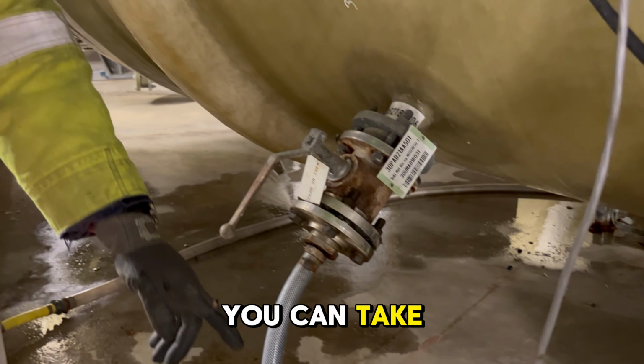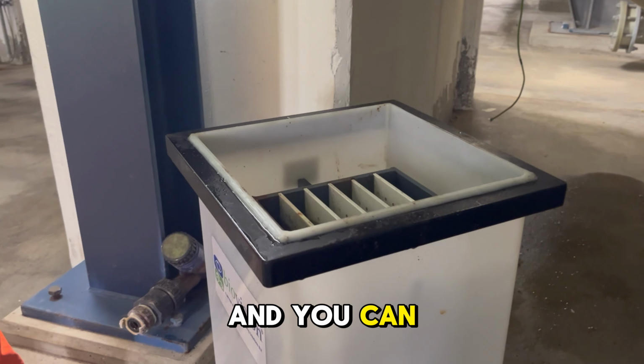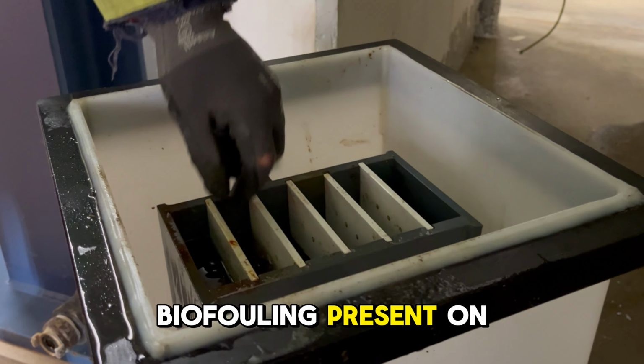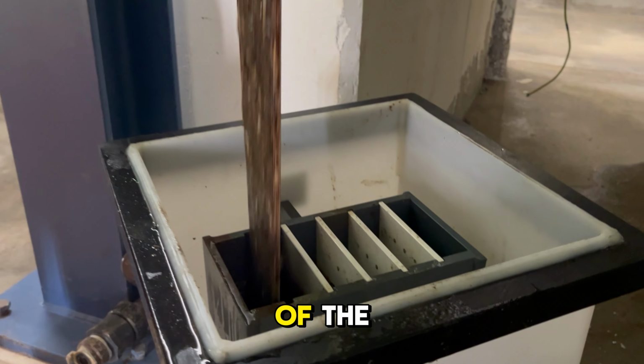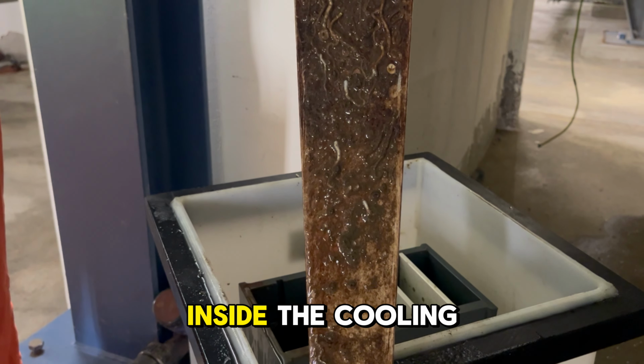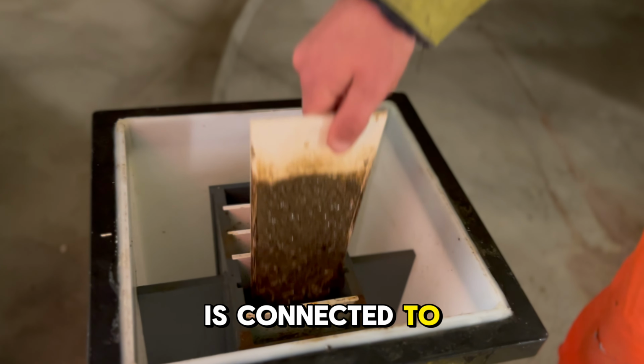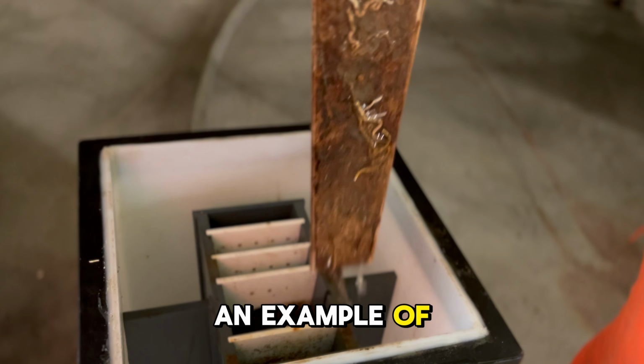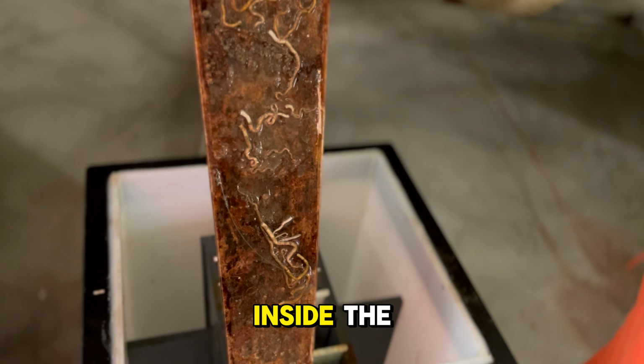In the Biovision monitor you can take out the coupons quite easily, and you can see if there's biofouling present on the coupons, which is representative of the fouling situation inside the cooling water pipe it is connected to. So this is an example of one of the biofouling coupons inside the Biovision monitor.